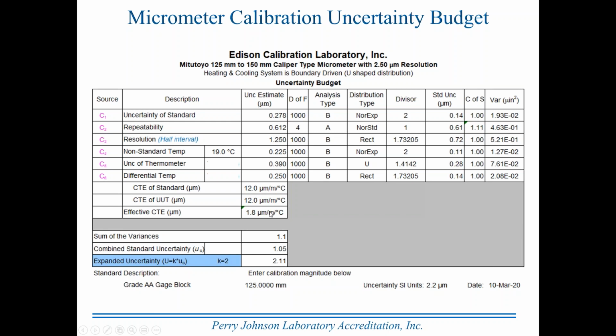We get down here the effective CTE from these coefficients. That's calculated into these numbers. We wind up with a sum of variances of 1.1. Combined standard uncertainty, 1.05. Expanded uncertainty would be the coverage factor multiplied by that, and we get 2.11.